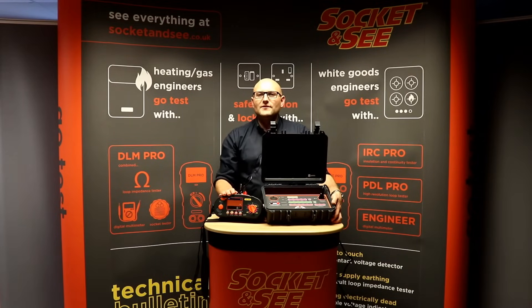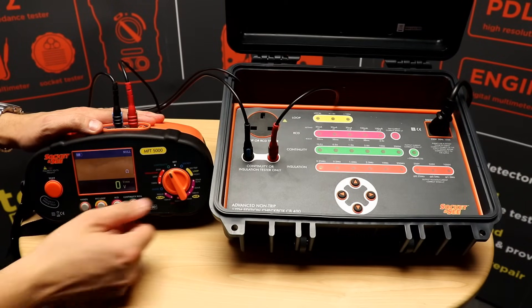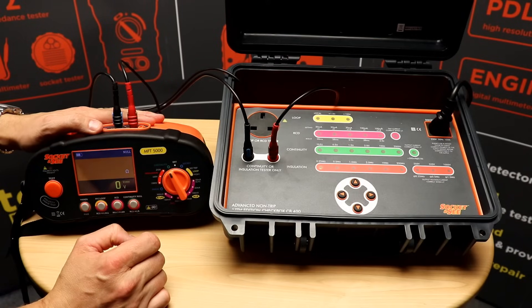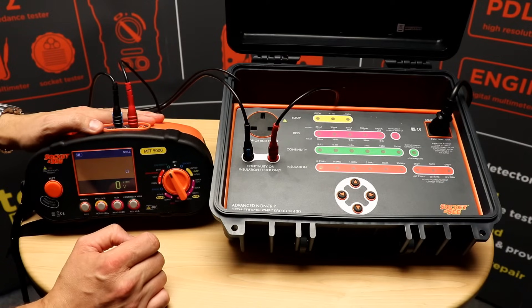For more information on these testers see everything at www.socketandsee.co.uk. First off I'm going to use the CB400 checkbox to check the ongoing accuracy of the MFT 5000's insulation test. The CB400 checkbox doesn't just check the resistance being measured, it checks the output current of the tester.